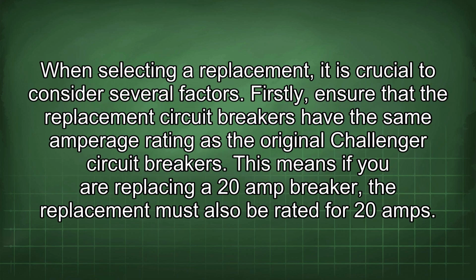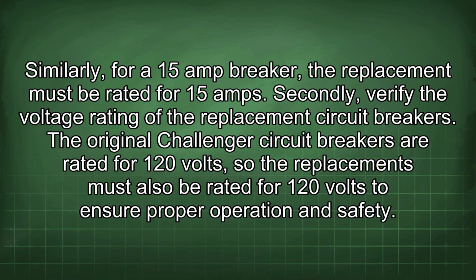When selecting a replacement, it is crucial to consider several factors. Firstly, ensure that the replacement circuit breakers have the same amperage rating as the original Challenger circuit breakers. This means if you are replacing a 20 amp breaker, the replacement must also be rated for 20 amps. Similarly, for a 15 amp breaker, the replacement must be rated for 15 amps. Secondly, verify the voltage rating of the replacement circuit breakers. The original Challenger circuit breakers are rated for 120 volts, so the replacements must also be rated for 120 volts to ensure proper operation and safety.